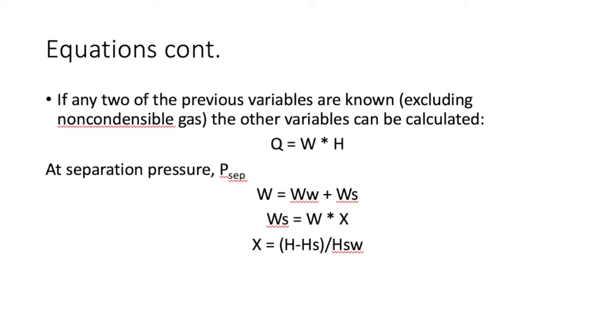We use these variables in the following equations. The first equation is exclusively for saturated conditions — when a liquid and vapor mixture exists together at a given temperature and pressure. If any two of the flow characteristic variables are known for a well, the others can be calculated, where heat flow equals total mass flow times fluid enthalpy. At separation pressure, total mass flow equals steam plus water flow, and steam flow equals total mass flow times the dryness factor.